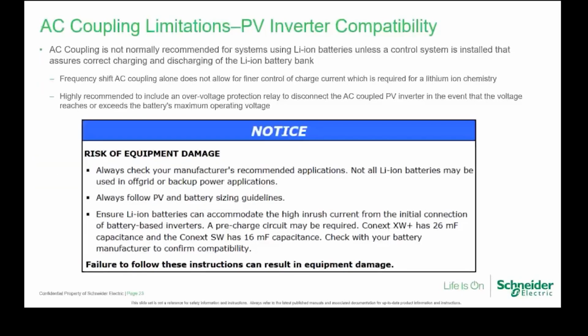Also, AC coupling is not normally recommended for systems using lithium-ion batteries, unless a control system is installed that assures correct charging and discharging of the lithium-ion battery pack. Basically, lithium-ion batteries are a bit more finicky when it comes to charge and discharge rates, and frequency shift AC coupling alone does not allow fine control of the charge current. So you need to put in some sort of suitable battery management system that can regulate the charging and discharging, and can also connect back up to the XW to turn it off in case of emergencies.